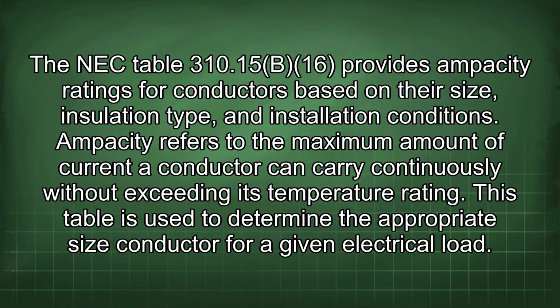The NEC Table 310.15(B)(16) provides ampacity ratings for conductors based on their size, insulation type, and installation conditions. Ampacity refers to the maximum amount of current a conductor can carry continuously without exceeding its temperature rating. This table is used to determine the appropriate size conductor for a given electrical load.